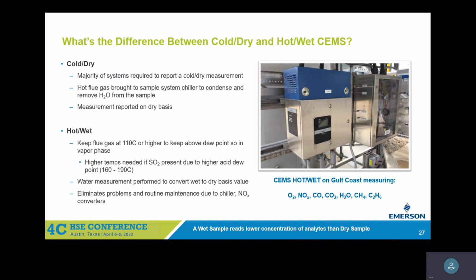So the key there is that you have to keep every bit of the line heated. As soon as you get a gap, you get condensation. So that's one thing. But it really simplifies it. It shrinks the system, and you can get it closer to your sample point. There's a lot of advantages for it. Less real estate, less things to go wrong. If you use a sample pump, you still have maintenance on the sample pump.